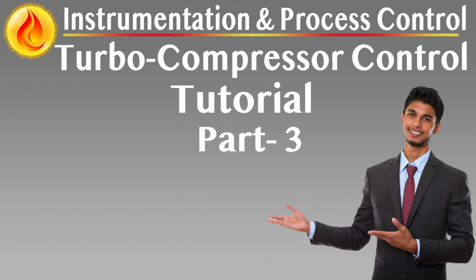Dynamic rebalancing. During changes in plant demand or process disturbances, the TCCS automatically redistributes load, decreasing speed on compressors approaching surge, increasing speed on compressors with more surge margin. This keeps the fleet operating within safe and stable boundaries. Fault tolerance. If a compressor trips or a surge margin sensor fails, the load sharing logic instantly rebalances among remaining trains. Alarm conditions are logged and displayed on the HMI and DCS.